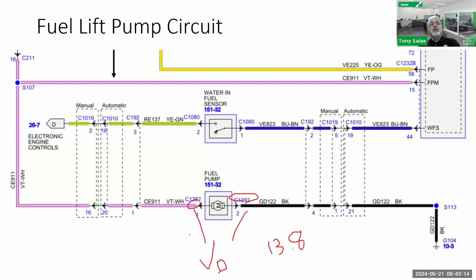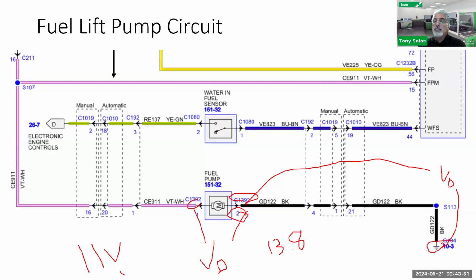So if I don't, then I'm going to do a voltage drop test across terminal 2. I'm going to put my meter right here and take it to ground. So if I have, using my crude example, 11 volts - and these numbers aren't unrealistic, I've seen 11 volts going to a pump - the question is, where is my high resistance at? Why do I have low voltage going to the pump? Then it's time to test. I can back probe terminal 2 and go from terminal 2 over to ground, checking voltage drop across there.